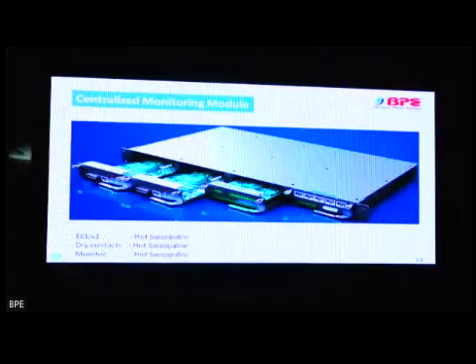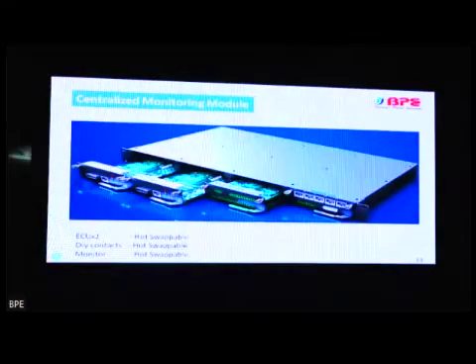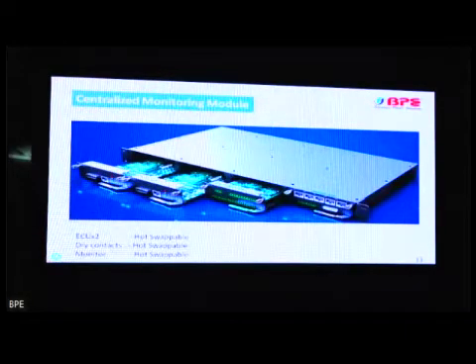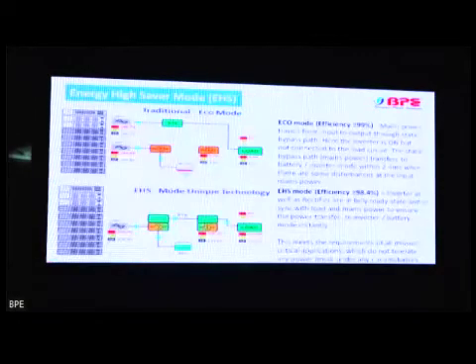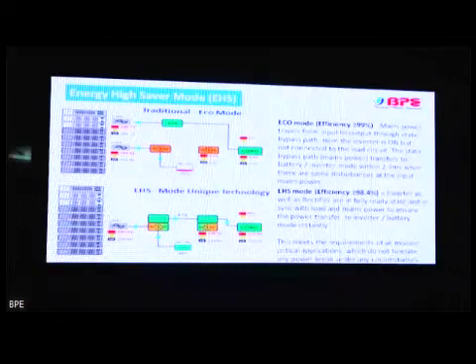We can parallel up to 6 units. This is about the redundant controller. We have a redundant controller here. Suppose we pull one controller, the UPS will still work, and if any one of the controllers fails, the UPS will still work. And there is a daisy chain also, so that you need not take a shutdown of the UPS for adding or removing any UPS from the site.